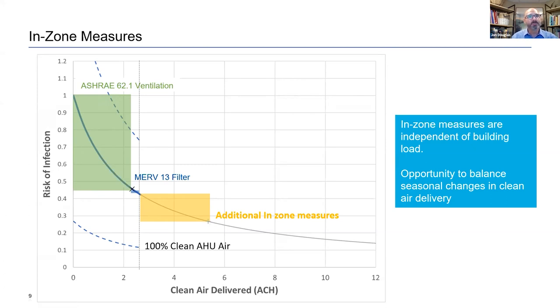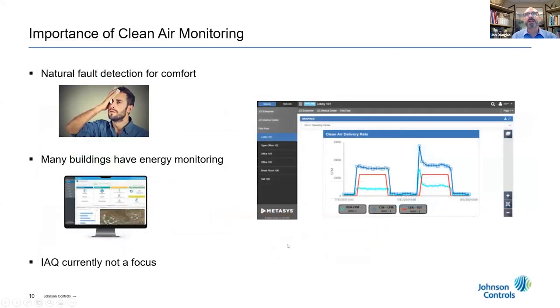So once you've got all this in place, it's important to think about what you do after you install your equipment. It's important to really think about monitoring. The reason I say that is that HVAC systems are primarily designed for comfort, so we actually have natural fault detection for buildings. If your HVAC stops working, people get hot or cold and they start complaining, the maintenance is notified and somebody goes and fixes it. Also, we've got a lot of focus on energy efficiency. Most large building automation systems, even most medium-sized building automation systems, have energy monitoring. So there are alarms out there that tell you you're consuming too much energy.